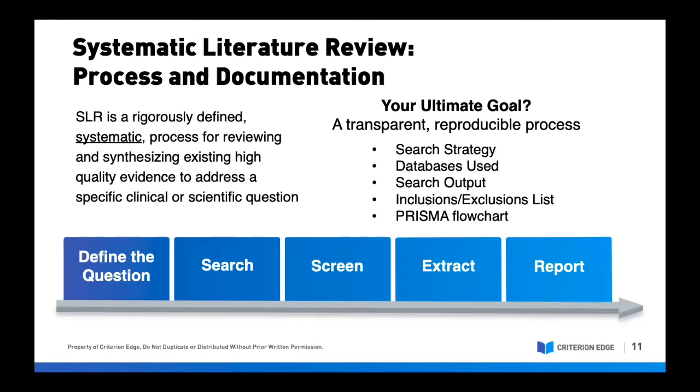So as we're thinking about the different processes of the systematic literature review, the first systematic literature review we discussed earlier was for the state of the art section of the SVR. This is how you're going to define the questions and identify your PICO terms: your population, intervention, comparators, and outcomes. So with the help of a qualified reference librarian, you will need to design a search using proper MeSH terminology and a robust search platform that allows you to search across multiple databases, from PubMed to Embase to multiple different databases that are out there.